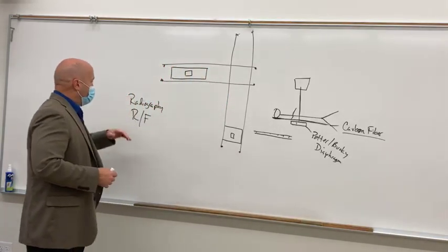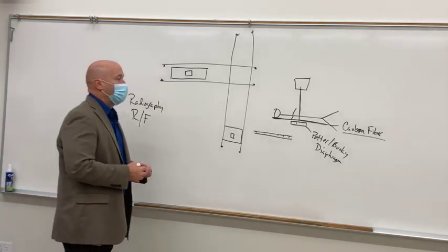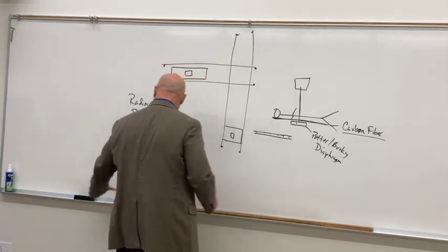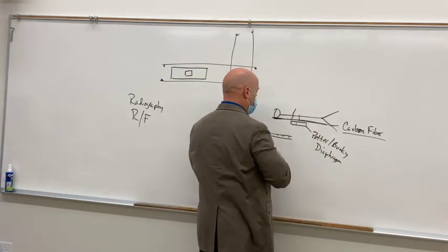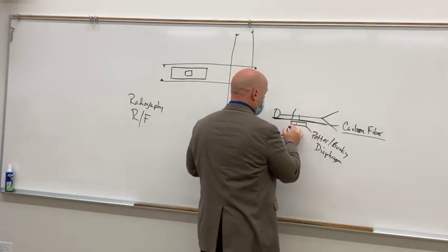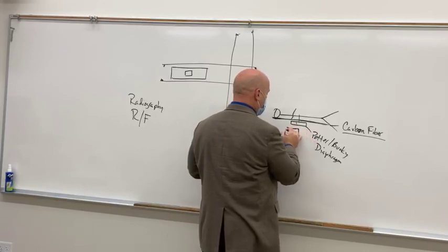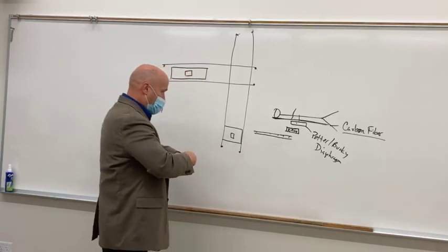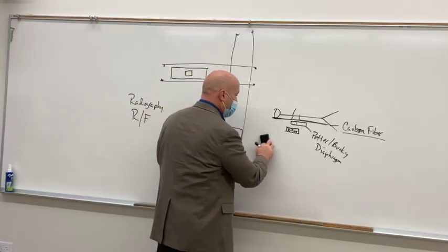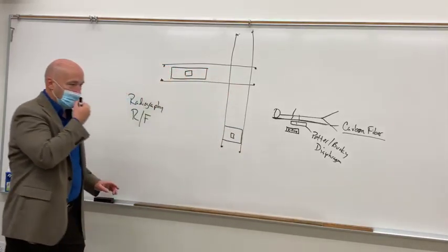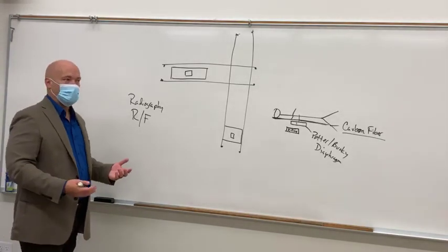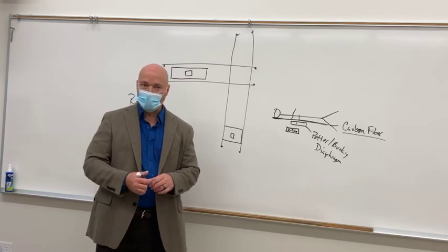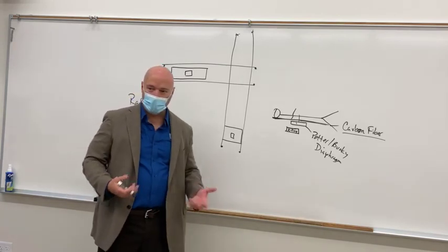So in fluoroscopy rooms, everything is reversed. You don't have an x-ray tube above the patient, you have an x-ray tube below the patient inside the table itself. So this is the x-ray tube. Now, our Potter-Bucky diaphragm has some components in it that you don't want to x-ray if you're not intending to x-ray them.